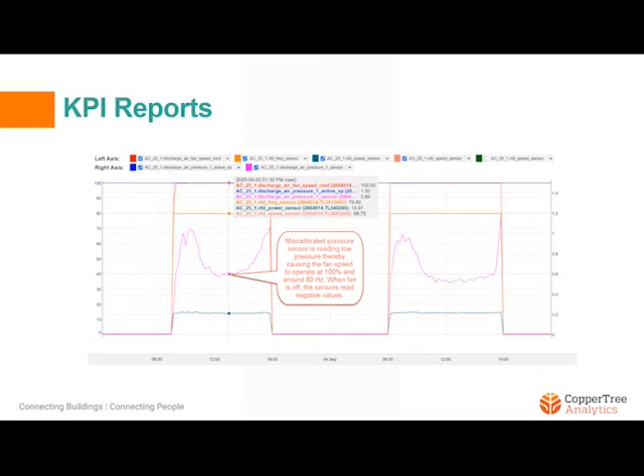What I'm interested in showing you here is the pink line, which is the static pressure sensor. The static pressure sensor reads negative values when the fan is off, which is what we detected. And when the fan is on, it reads a pressure reading. However, that reading is always really lower than what the actual pressure is. Now, what does this do? This tells the fan that the pressure is always below the active set point, causing the fan to ramp up to really high speeds. And we were noticing fans in this building running around 80 hertz. That's a lot of electricity consumption. And with the additional airflow, a lot of excessive thermal consumption as well.